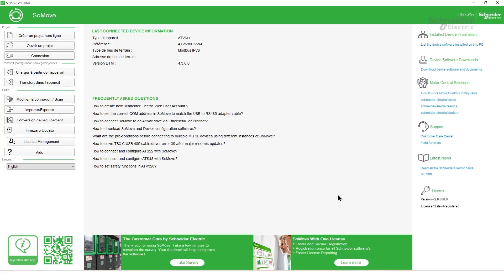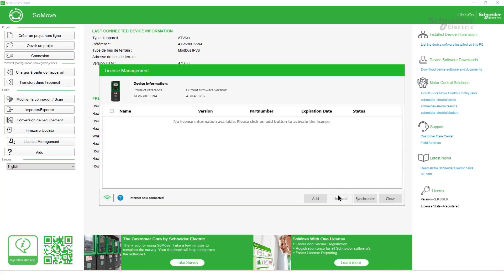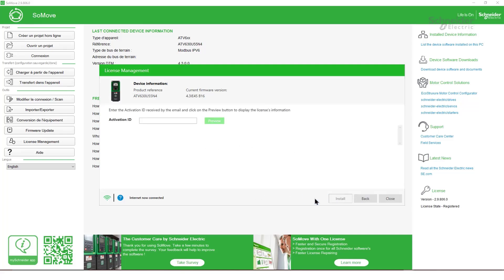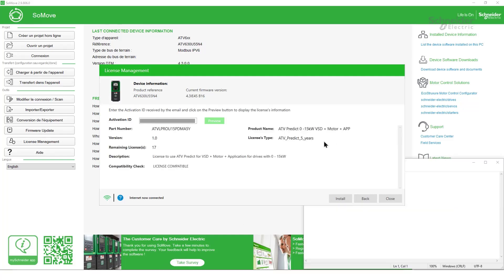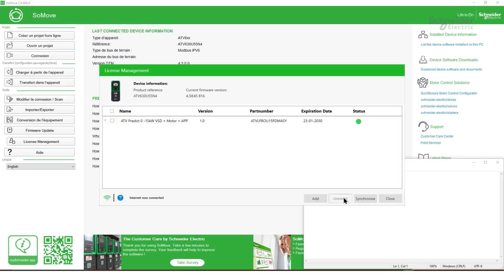SoMove will then display the License Management window for the connected drive. Click the Add License button and enter the activation ID. After adding the license to our system, we can see its type, product name, and description clearly displayed in our interface. Click Install. If the license is added correctly, the status will be green.